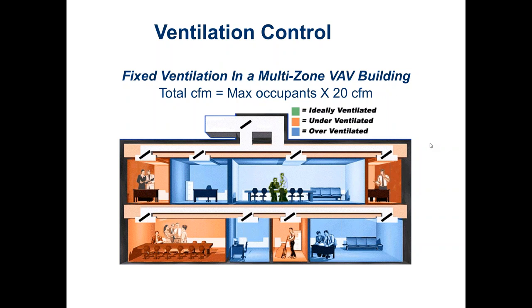On a VAV-type zoning system, we'd have dampers in all particular zones. What happens is we still ventilate for the maximum number of occupants at all times. There are two problems: if rooms are unoccupied, we're still ventilating them because code told us to. And second, as we slow the VFD down on a VAV system, we inadvertently bring less outside air into the intake, so we could be underventilating at certain times. In this drawing, spaces in blue are overventilated, orange is underventilated — very few spaces get the exact amount of air they need.